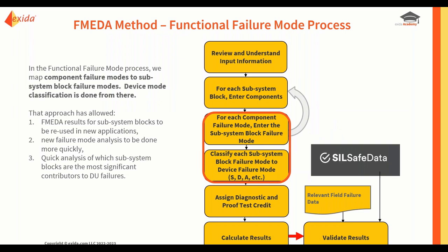And I suppose the advantage of doing this is, again, we had a customer last year who came to us who needed to apply IEC 61508 to their design, but also the industry they were in had a specific EN standard that they needed to apply to their device. And out of that EN standard, they asked us to look at their design and figure out which blocks or which components might lead to a hazardous situation, specifically fire or high voltage. Because we did a block level functional failure process in the FMEDA, we were enabled to pin down which particular blocks in the design might potentially lead to these two particular hazards, and from that extract the information that the customer was looking for.